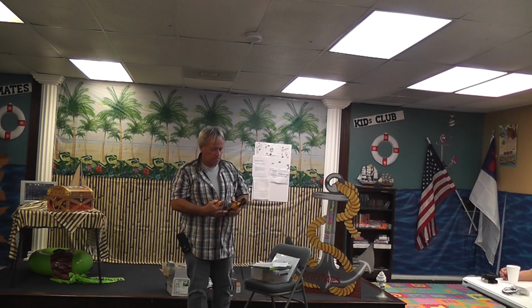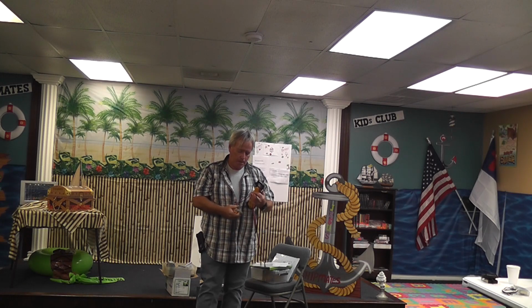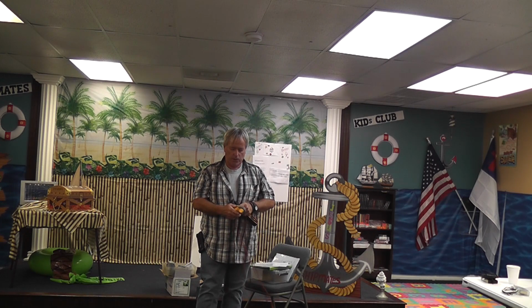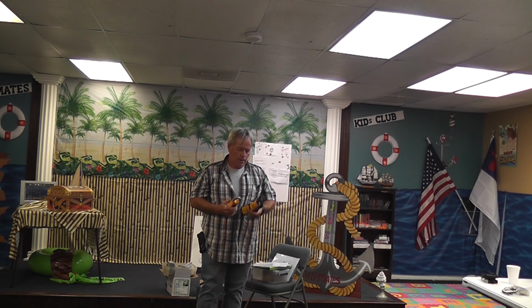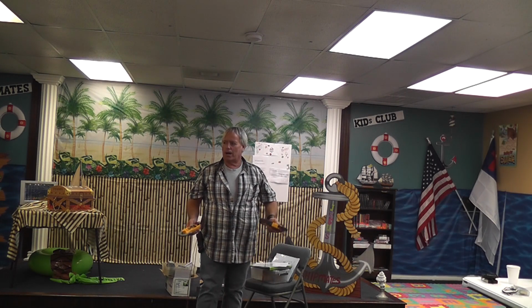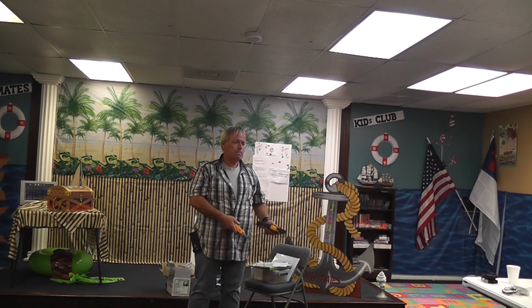They're rated in microfarads and voltages. Typical start cap only comes in 2 voltages, 370 and 440. 370 volts and 440 volts. So if you don't have a 370 volt capacitor, you could put in a 440, right? I don't stock 370s, because you can always put a 440 in place of a 370, but you can't put a 370 in place of a 440.